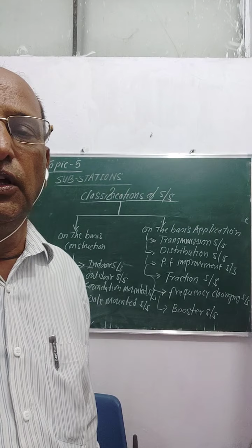Then distribution substation. As I have told you, there is primary distribution and secondary distribution. Primary distribution substations are those which are 33 by 11 kV with transformer rating up to 10 MVA or 12 MVA. Similarly, secondary distribution substations are 33 by 0.4 kV or 11 by 0.4 kV up to a maximum of 500 kVA transformer capacity. They may be foundation mounted for multi-storied buildings, and pole mounted for distribution in colony or residential areas.